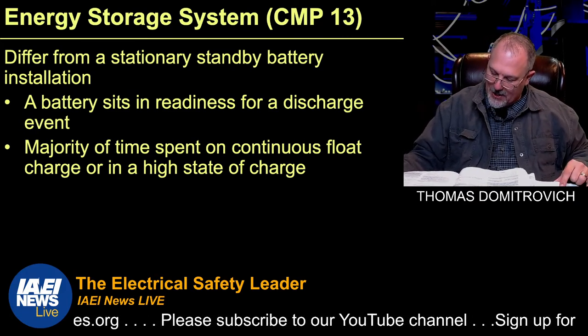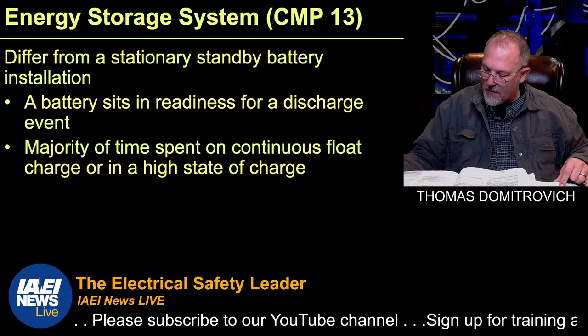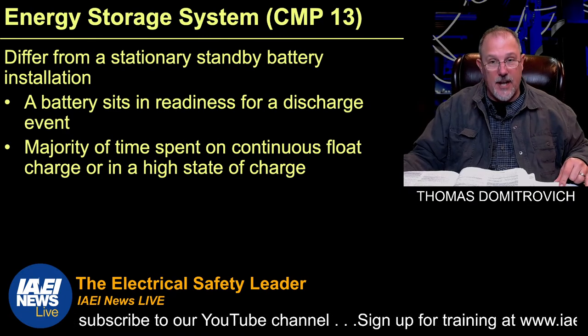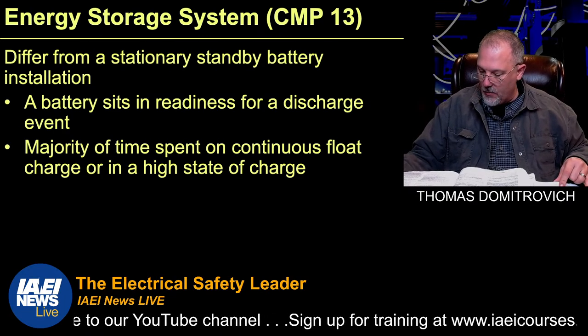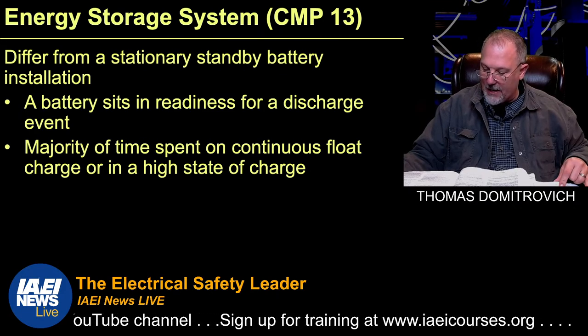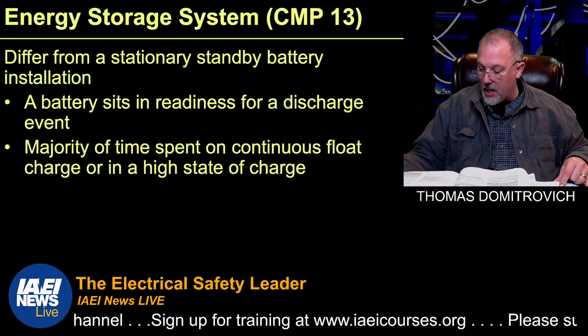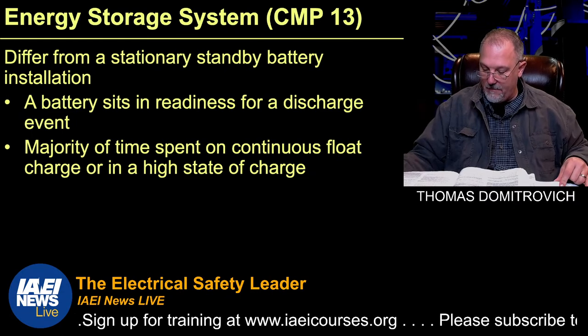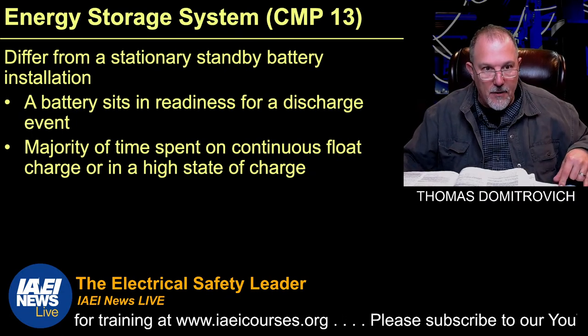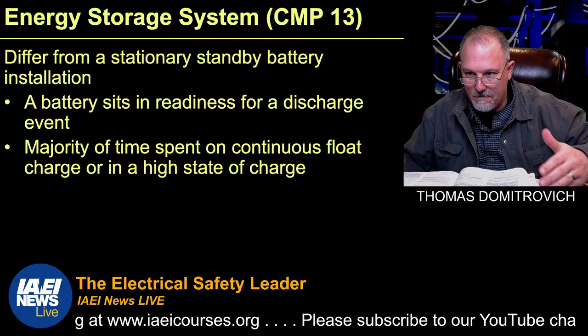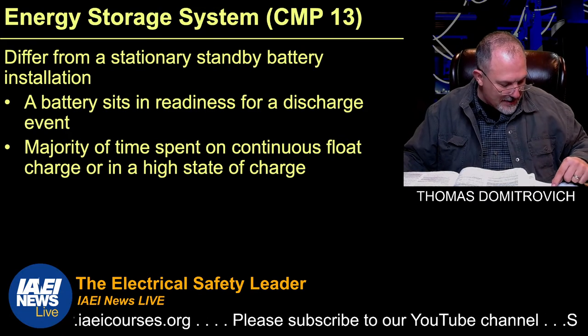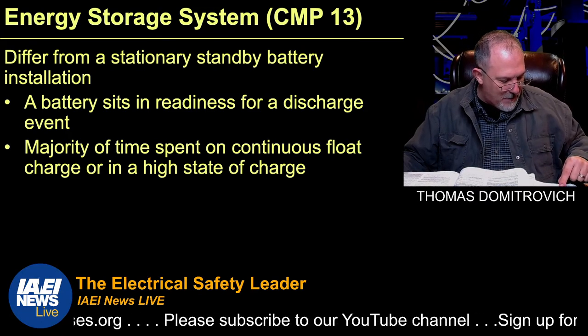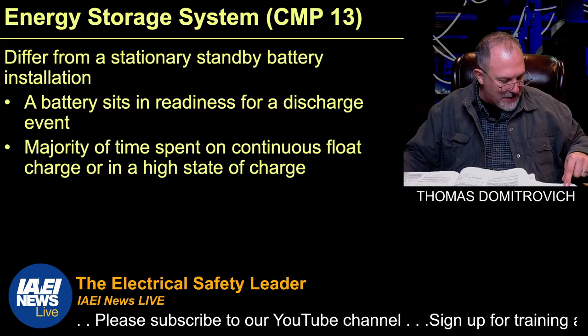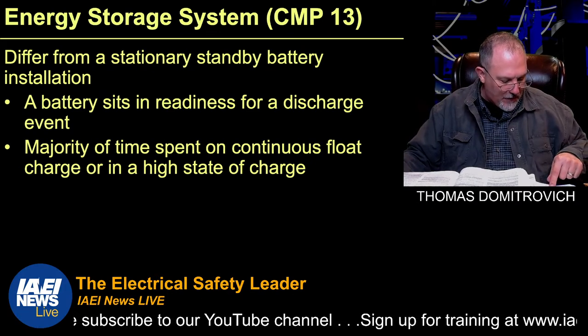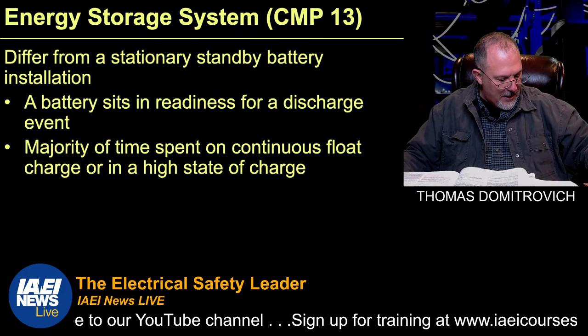In the 2020 code, it said these systems differ from other storage systems, such as a UPS, which is a power supply used to provide alternating current power to a load for some period of time in the event of power failure. They changed that to: these systems differ from a stationary standby battery installation, where a battery spends the majority of the time on continuous float charge or in a high state of charge.